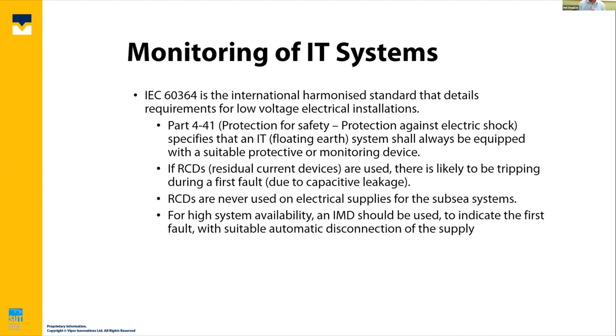So this device, the IMD, effectively monitors the integrity, or monitors the earthing, the leakage to earth, and then alarms in the first instance and gives the operator an ability to act on that alarm, either automatically or manually, to isolate the system.